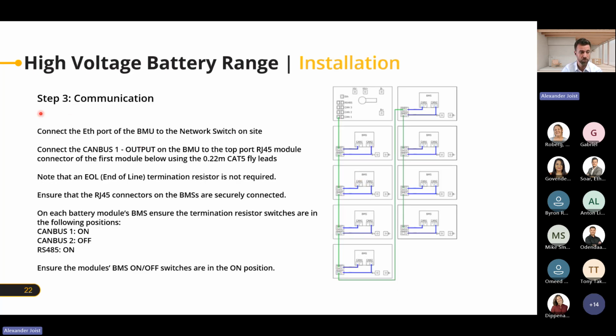Then the next step is to start with the communication wiring. Connect the Ethernet port of the BMU to the network switch — the Ethernet port we saw earlier, on the left side — to get an internet connection to your BMU or network. Then you start from CAN bus 1 and connect to the next battery. As we saw earlier with the BMS, those little blue lines are already made from the BMS to the battery front panel, so those connections are already in place — just check they're all connected properly. You just connect from CAN bus 1 down to each battery, all the way along.